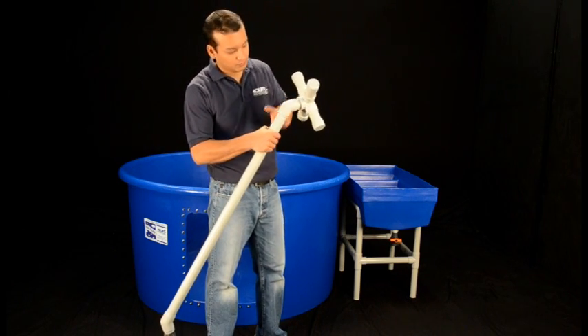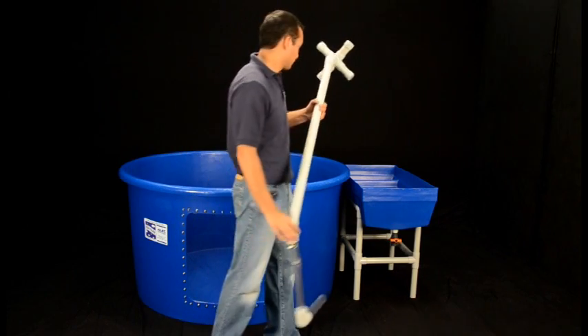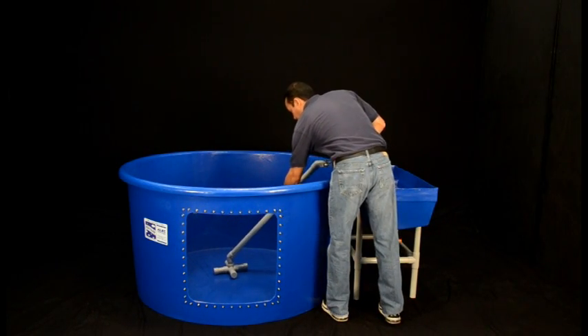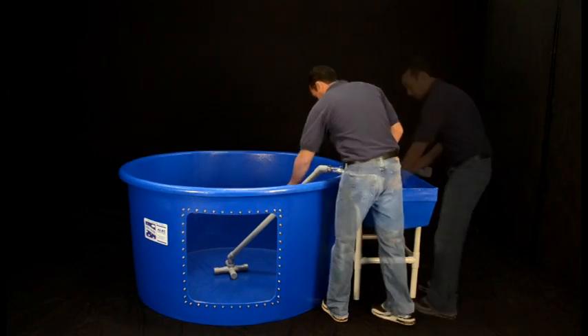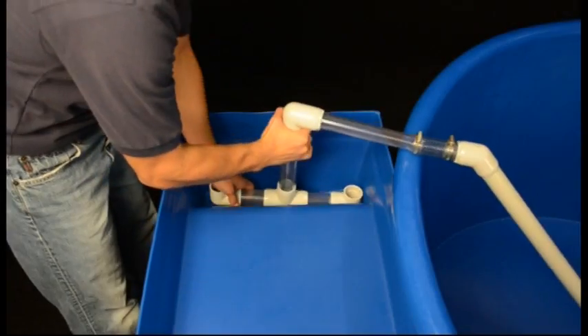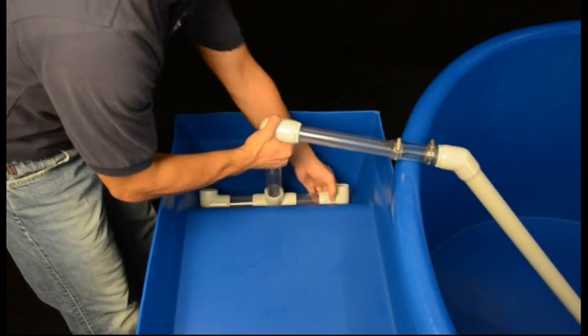Insert the water intake into the siphon assembly. Position the siphon assembly so that the water intake is flush to the bottom of the tank and centered. Place the opposite end of the assembly in the deep end of the clarifier table and attach the velocity reducer. Direct the velocity reducer outlets away from the weir, facing left.